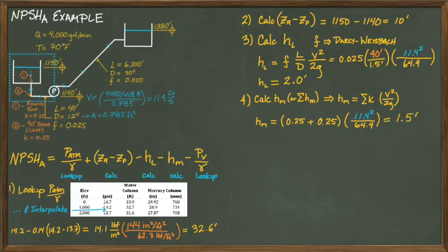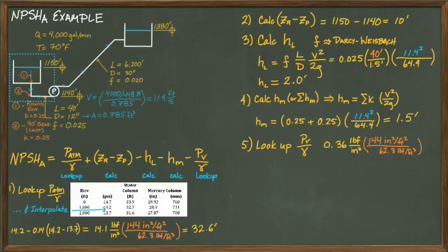Now we look up the vapor pressure head, which I find as 0.36 pounds per square inch. Vapor pressure is the amount of pressure that the layer of vapor exerts on the surface of water. All standing water has a certain amount of vapor pressure acting on it. So for this computation, we need to pull out the impact from the vapor layer. Once again, we multiply by 144 and divide by the unit weight of water at 70 degrees to get a vapor pressure head of 0.84 feet.